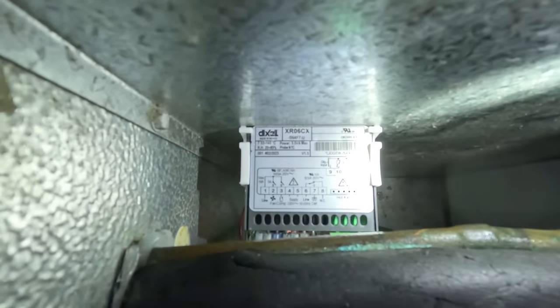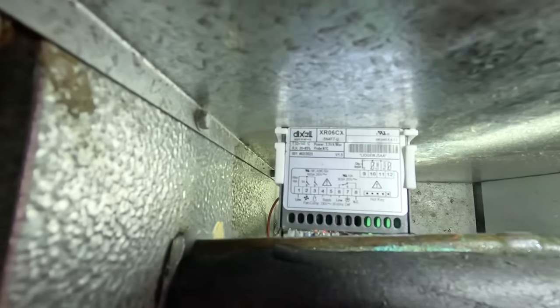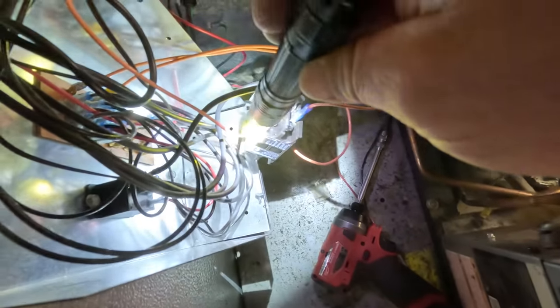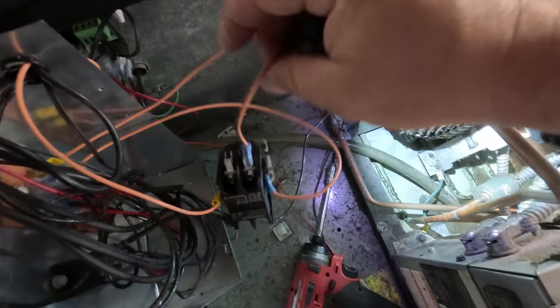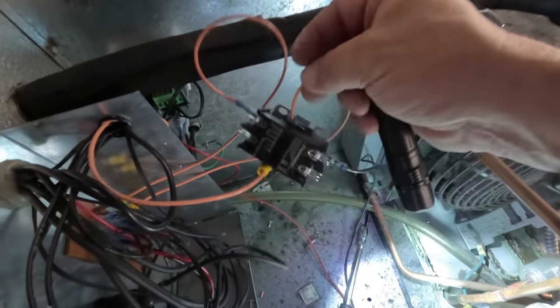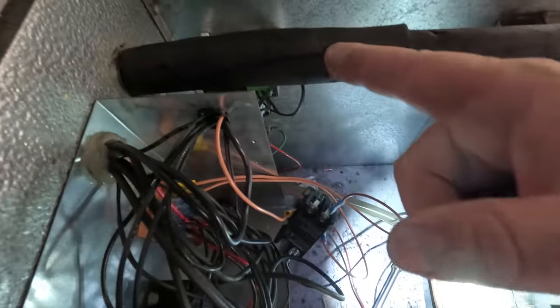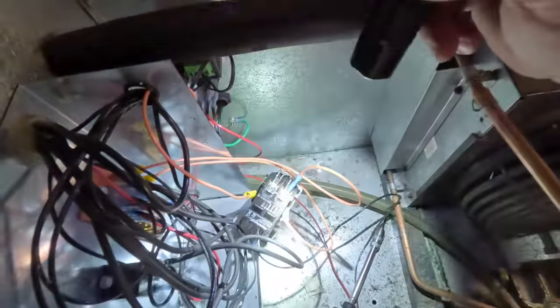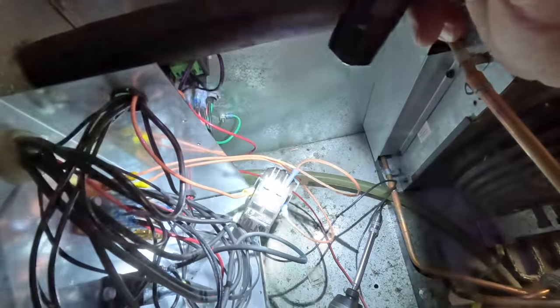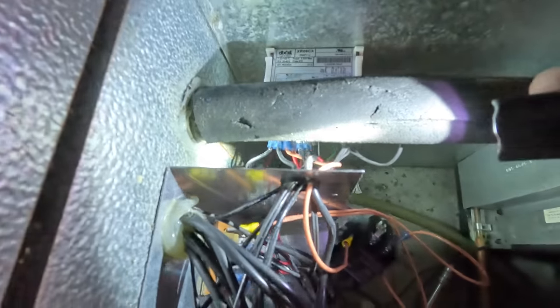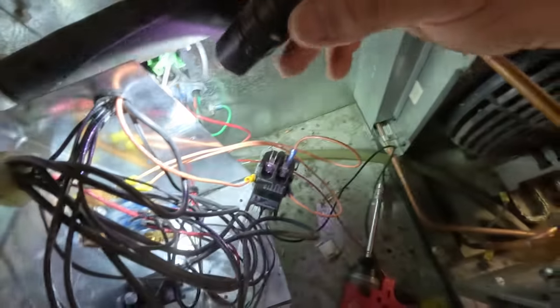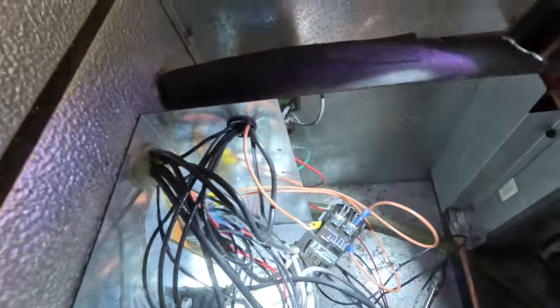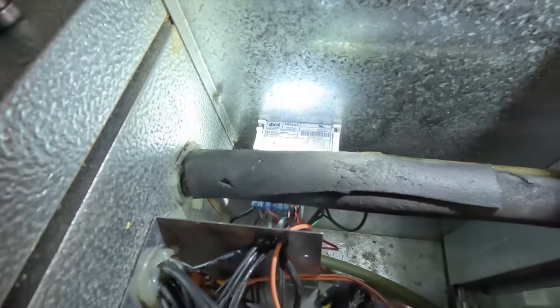Alright, so we've got the orange wire coming off what would be the compressor right there. That wire's coming over here and going to my contactor's coil. The opposite side of power going in there is coming off of the terminal strip over here. That's going to the other side of my coil. Then the power for the compressor is getting its power from the same place the controller's getting it from, passing through the contactor, going then on down to the compressor. Basically it's just an isolation. It's going to take, instead of the amperage, going through the little lightweight contacts inside the controller. They are going to go through, they're just going to control the coil voltage, which is still 240 volt, but there's no amperage behind it. It's just going to control the contactor. And we've got everything ran through, a little loopy-doop there, which I've got to get this other one up here and through one of the eyelets there. And then we'll mount this thing inside this box, put the cover back on, and everything will be good.